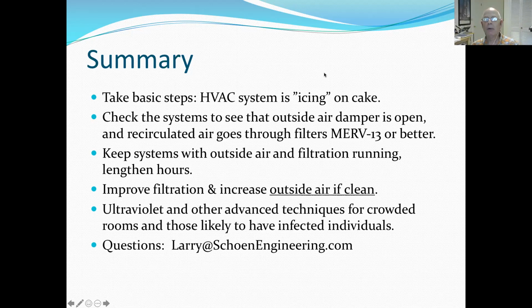So I've given you those numbers. Even though the codes would say 8 to 10, I would be looking in my facility for a minimum of 15, which is the old code. If your system can't do it and you're meeting the code, then operate what you have. But I would try to get it up to 15 if I could.